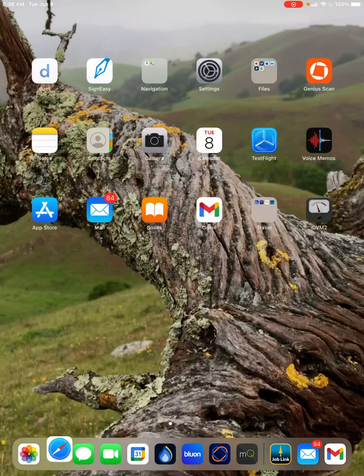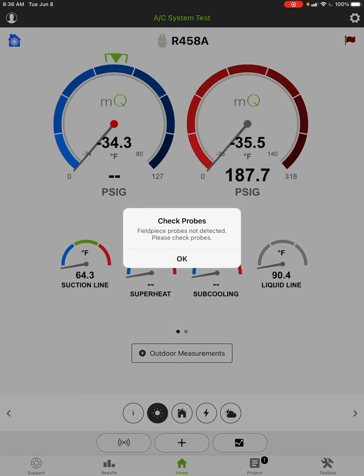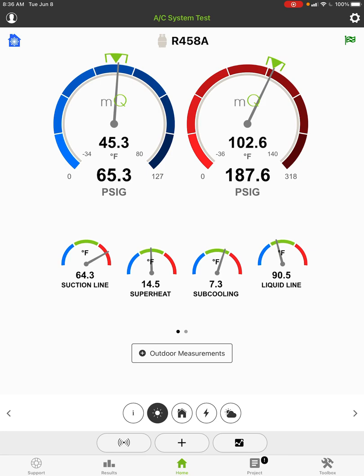In MeasureQuick, we're calculating average coil temperature because we're calculating where those targets should be for the high and low side temperature. We use dew point and bubble point in the background to calculate superheat and subcooling. Our app always agrees with other apps on superheat and subcooling because, like us, they're using dew point and bubble point. But the difference is we're displaying average coil temp under your gauge, which is much more representative of the temperature you should be looking for, especially if you're doing refrigeration.